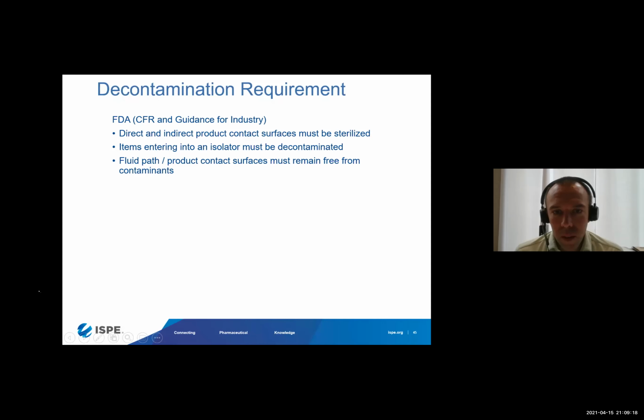So I took a look at the regulations again here. The FDA in the United States, through the Code of Federal Regulations and Guidance for Industry, specifically states direct and indirect product contact surfaces must be sterilized. No problem, that's our autoclave validation. However, it also adds that items entering into an isolator must be decontaminated. Well, that's either through surface decontamination of the sterilization wrapping using a wipe down or a spray, but more typically the vaporized hydrogen peroxide process.